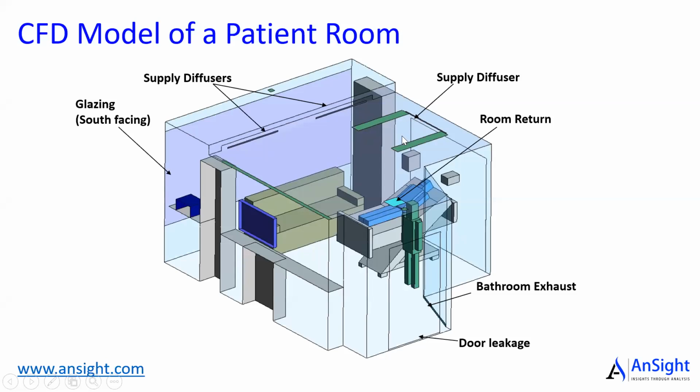And then we have two lights here. By the way, there is a small exhaust grille, or return, what we call it, to take the air out from there. Again, there is no set guidance on how large this grille should be and where it should be placed. The contractor goes and starts building this hospital and says, oh, wherever it feels good, wherever it looks good, just throw that grille there, okay?